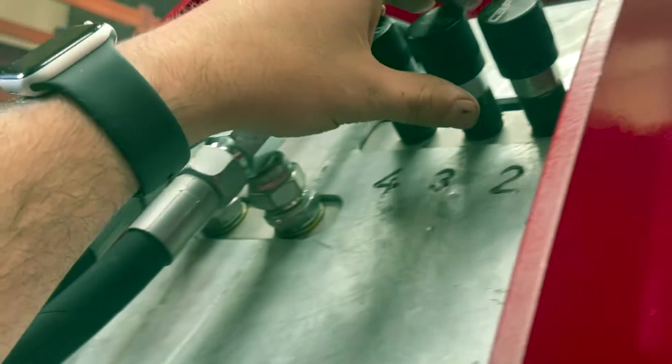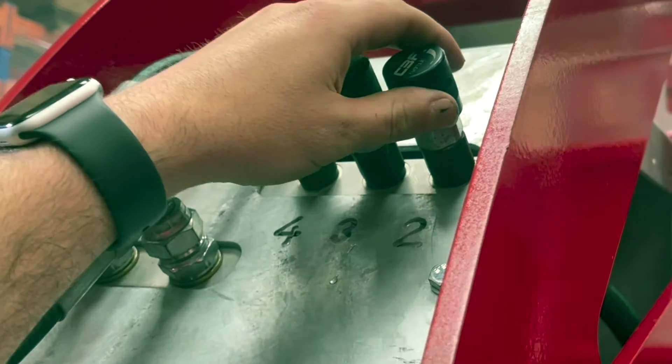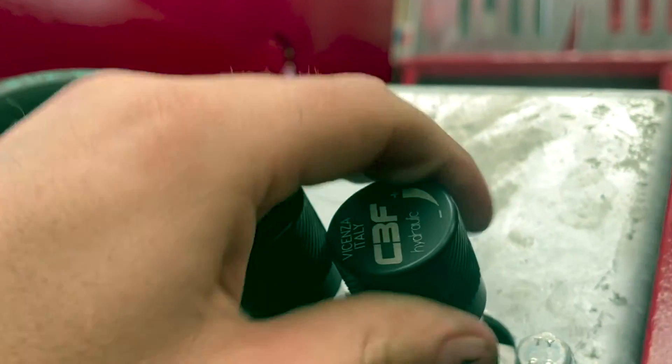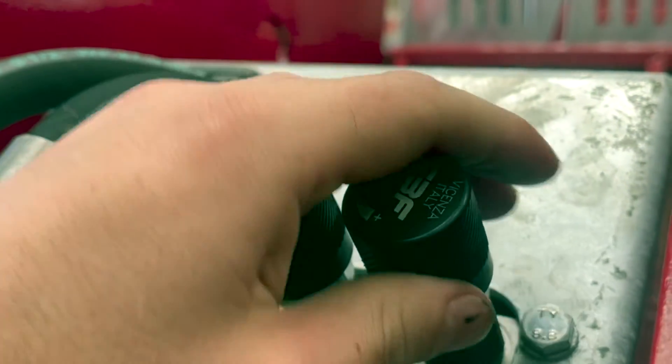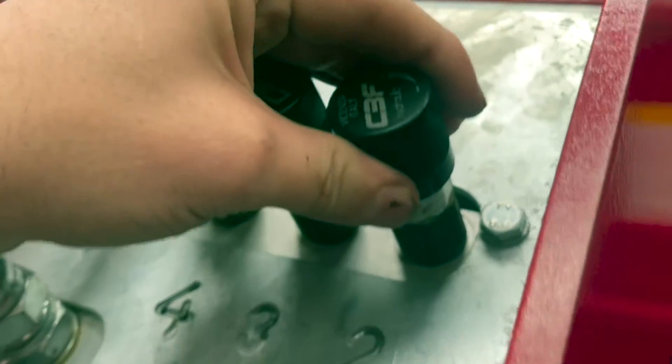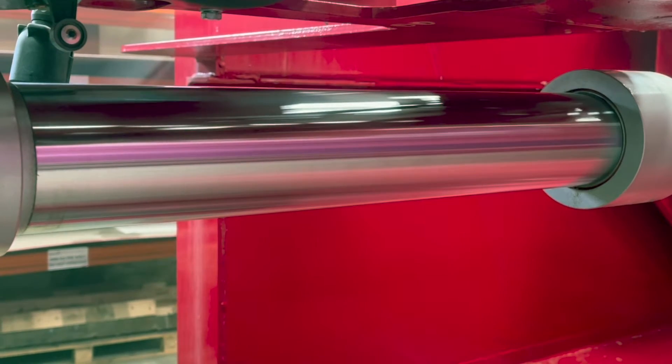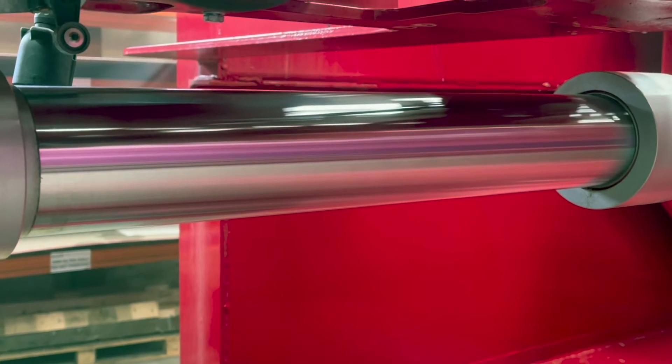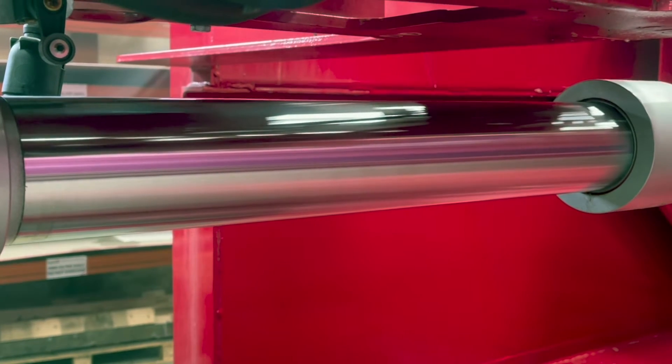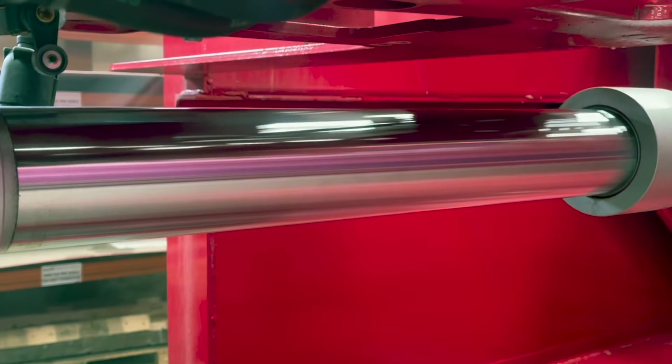To adjust the speed of stage number two, we simply use the flow control on the front. Anti-clockwise will increase the speed, and clockwise will reduce the speed of the ram. As you can clearly see, we can stop the ram from physically pushing out, or we can open the flow control right up, and you will see the speed of the ram stages start to increase.